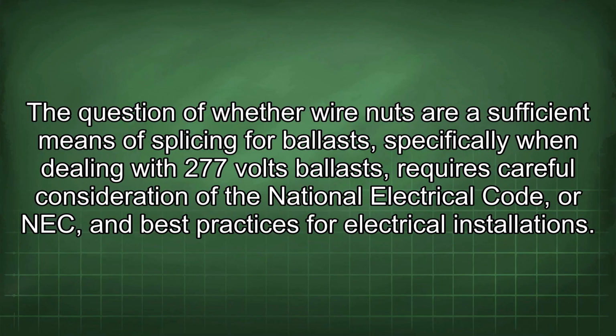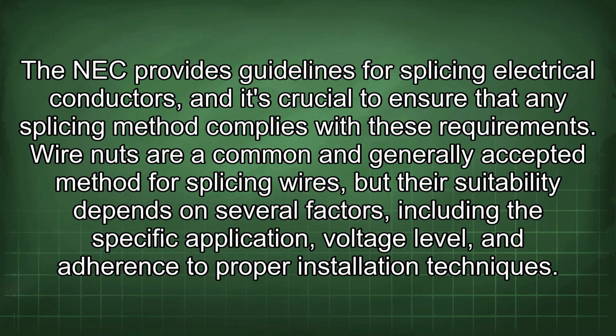The question of whether wire nuts are a sufficient means of splicing for ballast, specifically when dealing with 277 volts ballast, requires careful consideration of the National Electrical Code, or NEC, and best practices for electrical installations. The NEC provides guidelines for splicing electrical conductors, and it's crucial to ensure that any splicing method complies with these requirements. Wire nuts are a common and generally accepted method for splicing wires, but their suitability depends on several factors, including the specific application, voltage level, and adherence to proper installation techniques.